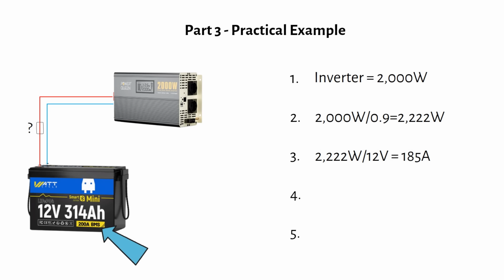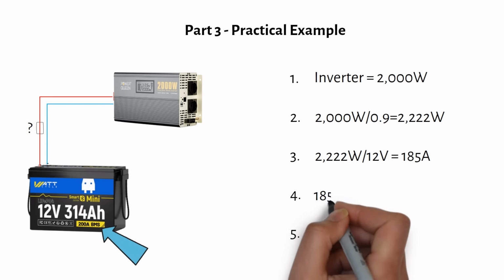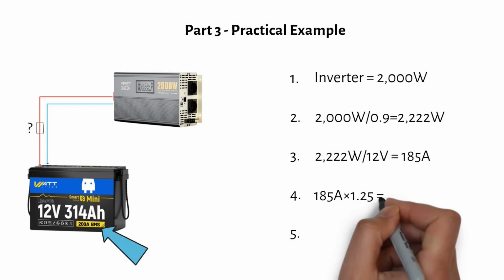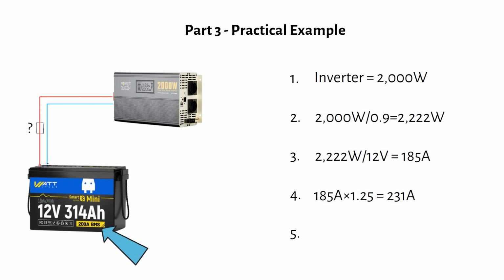Now we add the safety factor. 185 amps times 1.25 equals 231 amps. 231 amps is not a standard fuse size, so we round up to the next available fuse size, and that's 250 amps. That's your main fuse for the battery. Easy, right? Nowhere in that calculation did we look at amp hours of the battery. Not once. Amp hours does not decide the fuse size.